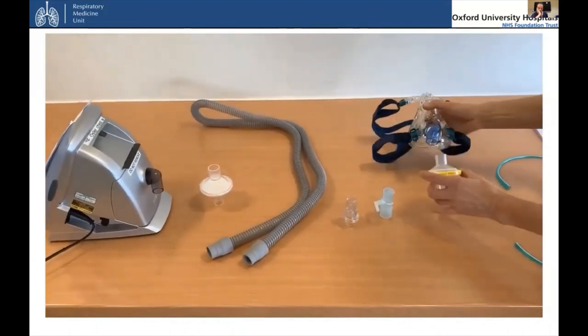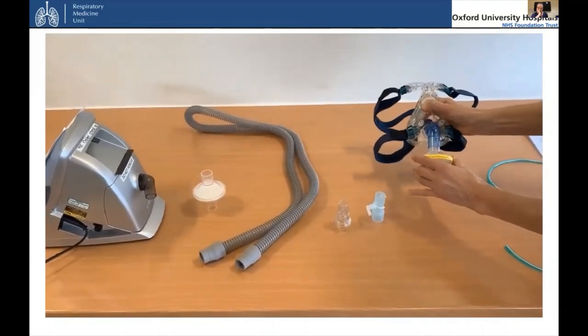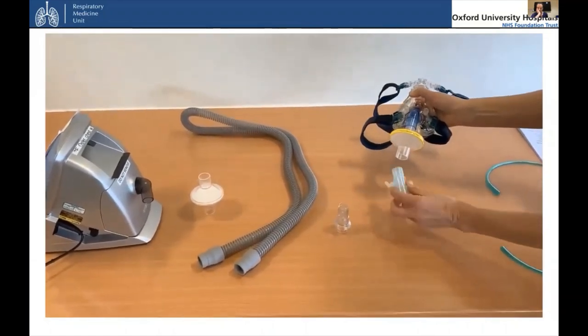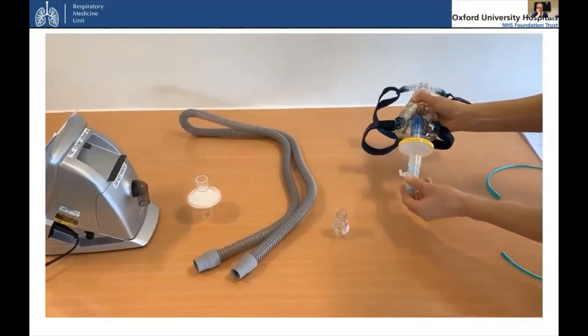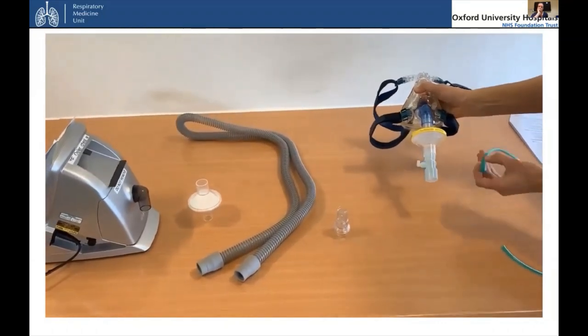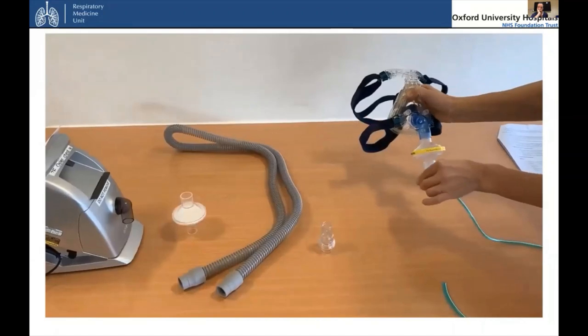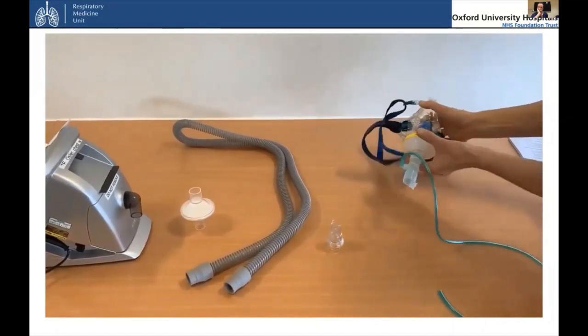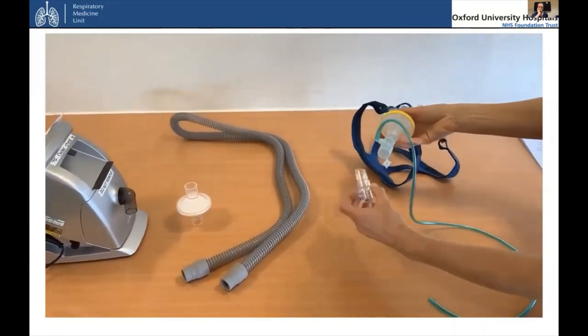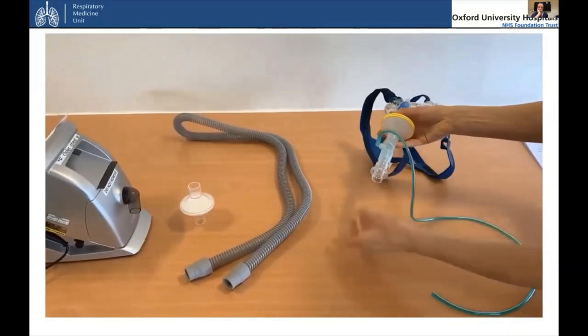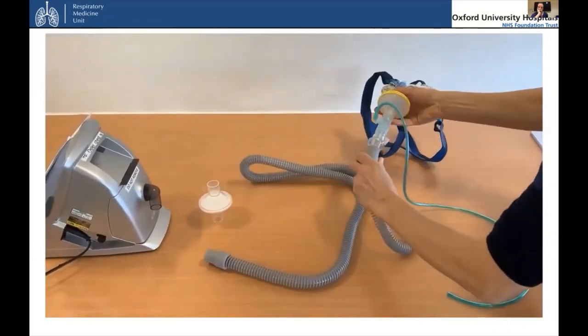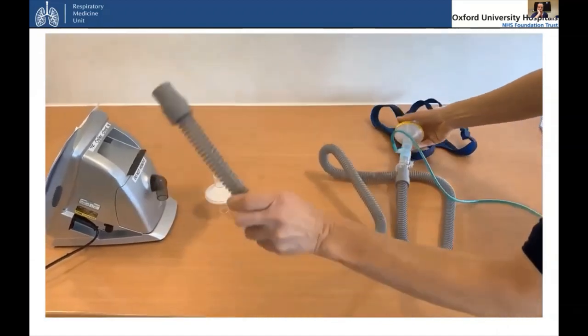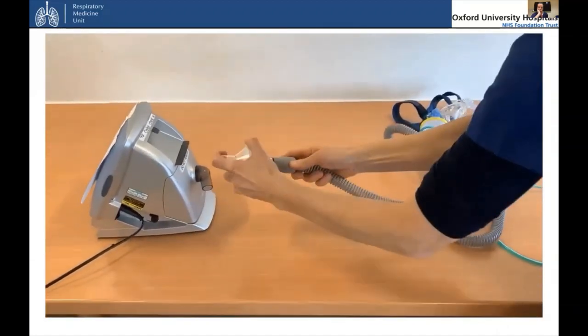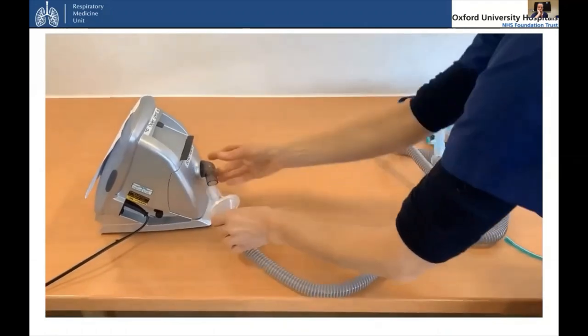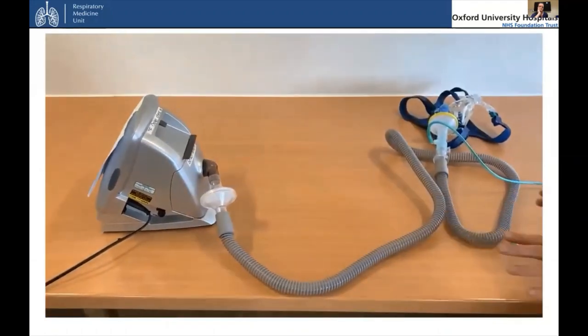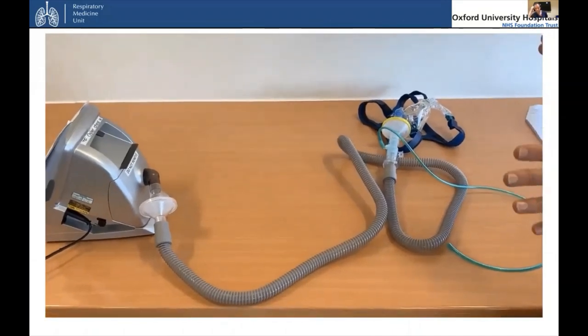So the filter is attached to the mask, followed by the oxygen connector, and the oxygen tubing can be attached but not turned on at the wall yet. The exhale valve is then fitted, followed by the ventilator tubing, and the second filter, which is attached to the machine. So you're now ready to set it up on the patient.